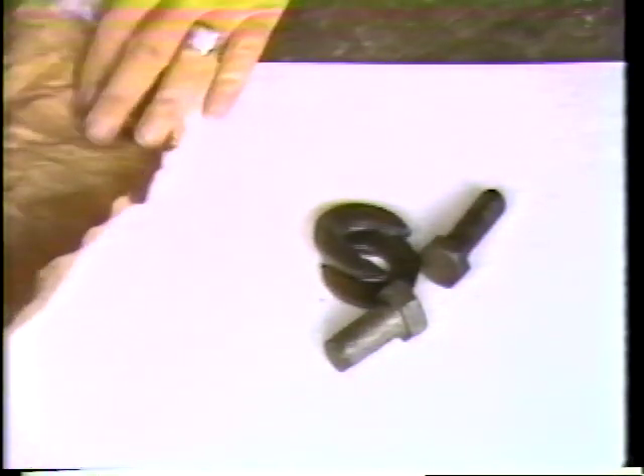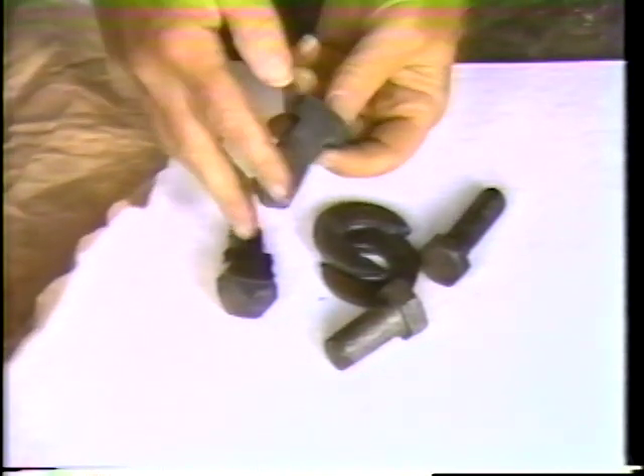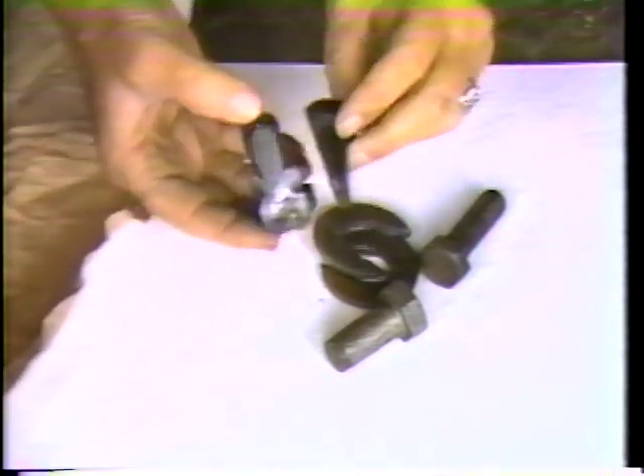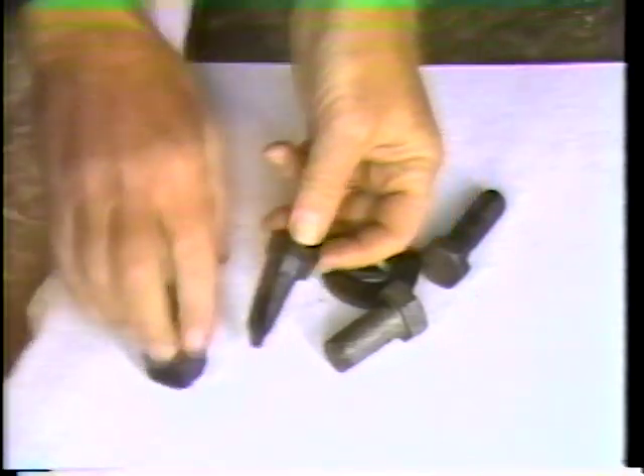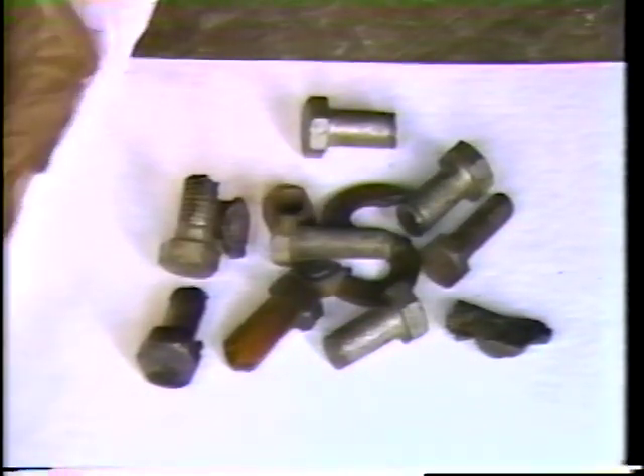This metal came up the conveyor. It was delivered to the number 2 pulverizer. You can see here that this metal got in underneath the plow, as did this, and could have caused severe damage if not detected. This all wound up in the metal trap, was exhausted out.